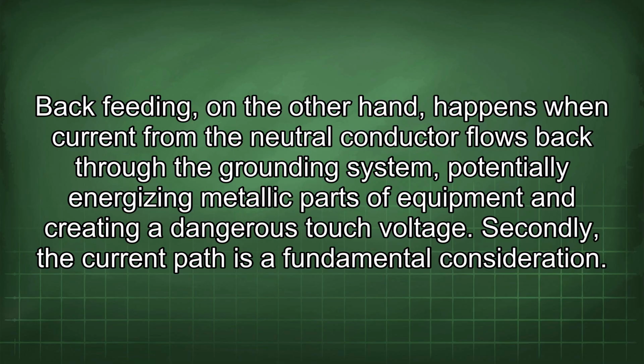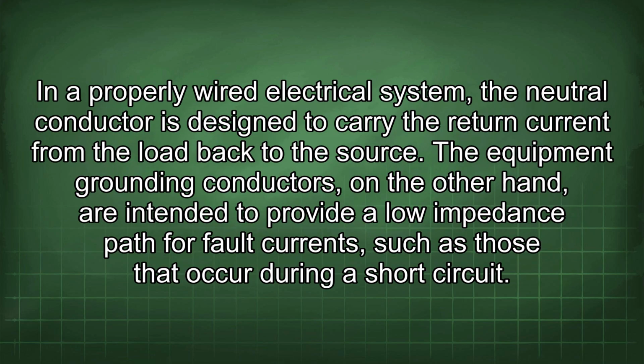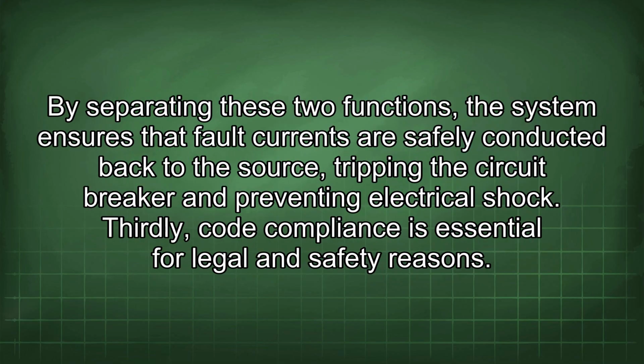Secondly, the current path is a fundamental consideration. In a properly wired electrical system, the neutral conductor is designed to carry the return current from the load back to the source. The equipment grounding conductors, on the other hand, are intended to provide a low impedance path for fault currents such as those that occur during a short circuit. By separating these two functions, the system ensures that fault currents are safely conducted back to the source, tripping the circuit breaker and preventing an electrical shock.